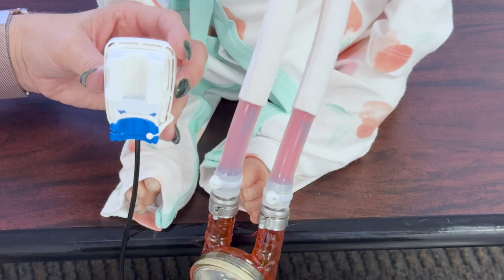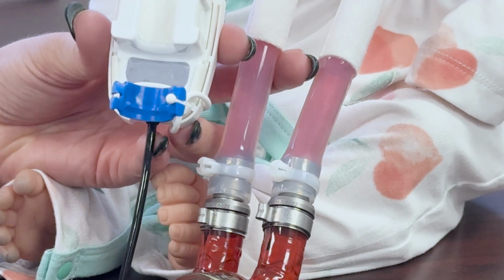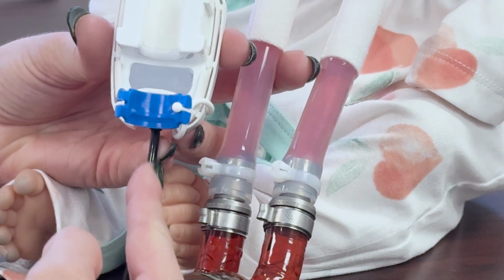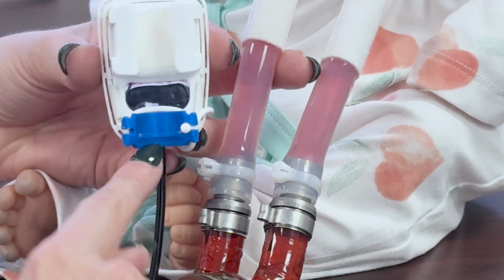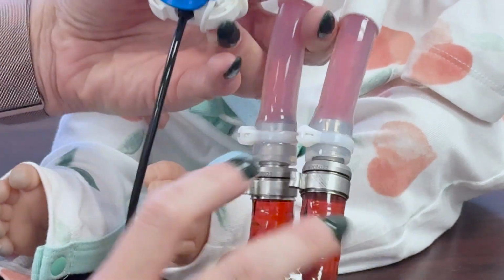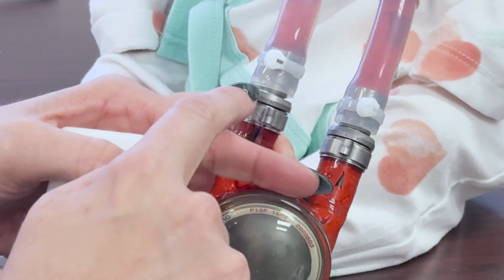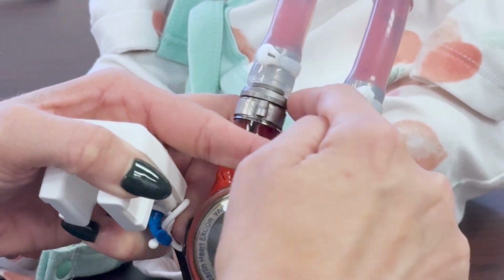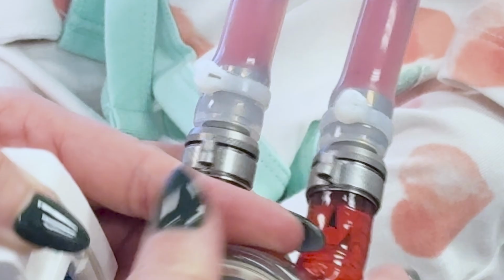make sure the black cord is going in the direction of the driveline. When placing your cannula inside the flow sensor, you want to make sure that the ledge of the flow sensor, which you'll notice is kind of like a little plastic ledge here, comes in direct connection with your titanium stub ledge. The plastic will sit right on top of the titanium.